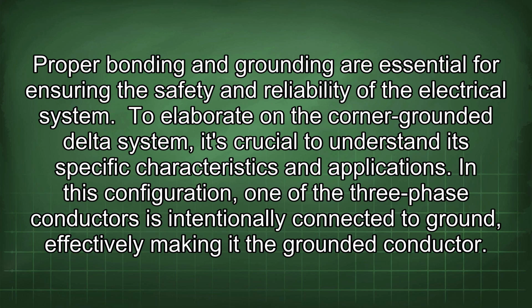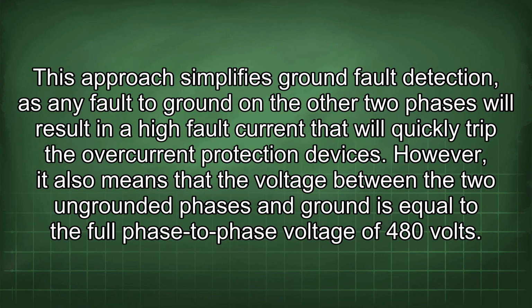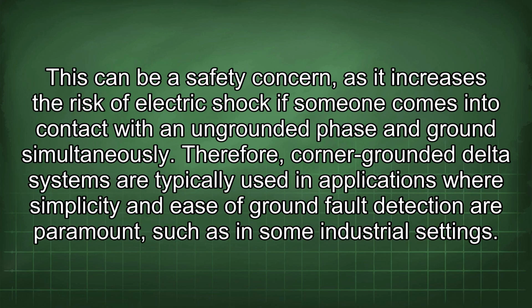To elaborate on the corner grounded delta system, it's crucial to understand its specific characteristics and applications. In this configuration, one of the three-phase conductors is intentionally connected to ground, effectively making it the grounded conductor. This approach simplifies ground fault detection, as any fault to ground on the other two phases will result in a high fault current that will quickly trip the overcurrent protection devices. However, it also means that the voltage between the two ungrounded phases and ground is equal to the full phase-to-phase voltage of 480 volts. This can be a safety concern, as it increases the risk of electric shock if someone comes into contact with an ungrounded phase and ground simultaneously.